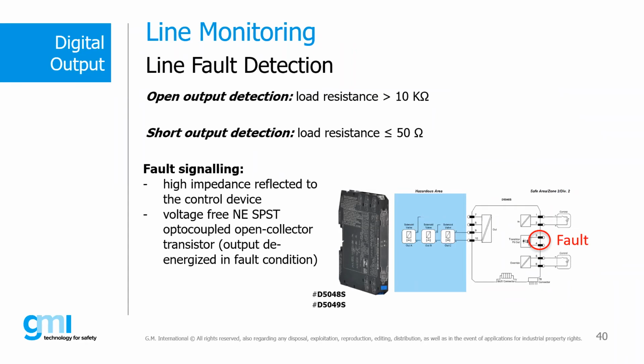Yes, also for digital out modules, GMI offers models with onboard line and load diagnostic to monitor loops in a hazardous area. The models D5048S loop powered and D5049S bus powered, based on the impedance of the load in the field, are able to check the health of the loop and, in the event of a fault, generate a signal to the PLC directly to the digital output card mirroring function, or through the classic voltage free contact to a dedicated DCS digital input card.